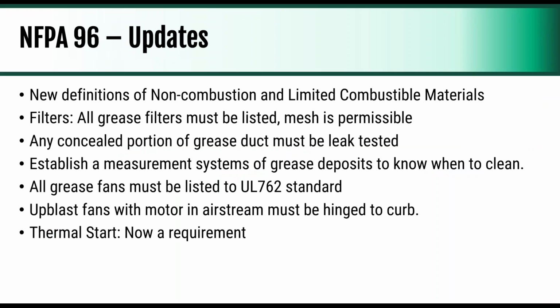NFPA 96 in Ontario, so the new building code, they adopted it, I think 2 years ago now, but it's effective January 1st. They adopted NFPA 96 version 2014, so it's not even the most recent standard, but that's typically how standards are adopted. I'm sure everyone's aware of that. There are some new definitions of non-combustible and limited combustible materials. I'm not going to go through them in detail, but prior, they just said basically a hood has to be 3 inches from limited combustibles and 18 inches from combustible materials, and they could have zero clearance to non-combustible materials. But they did not provide a lot of specific detail around it, whereas now they do.